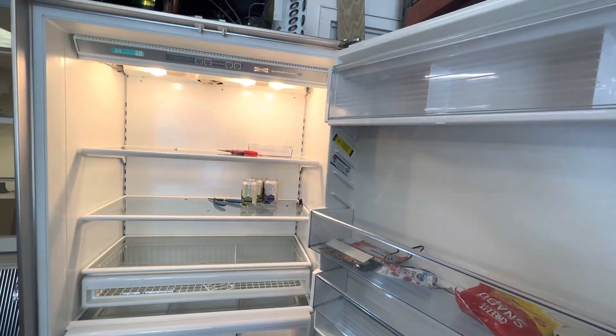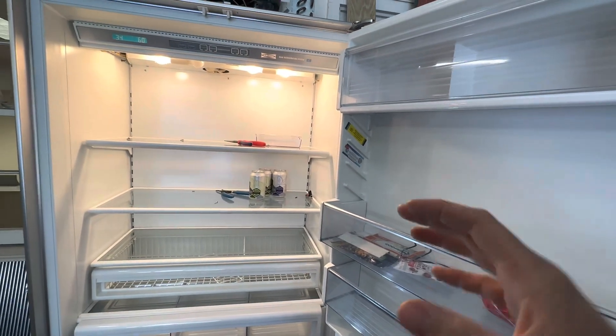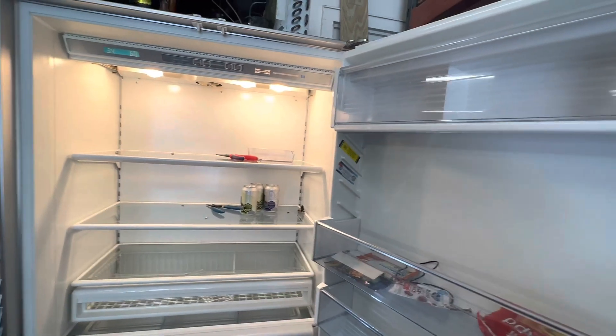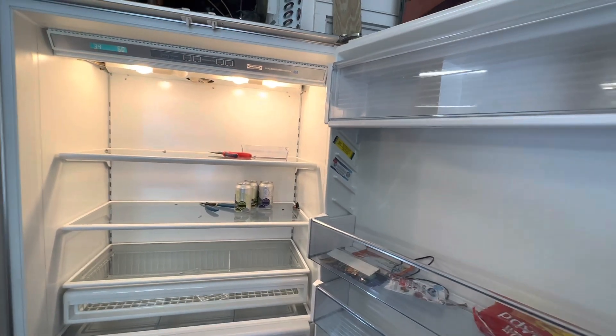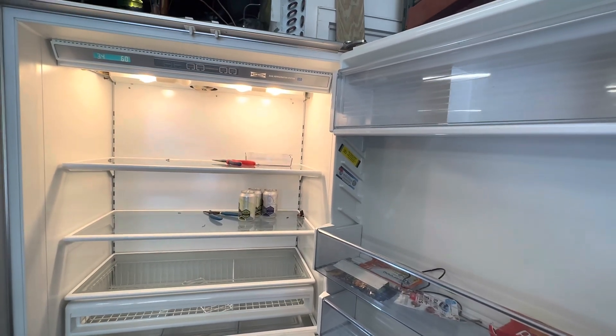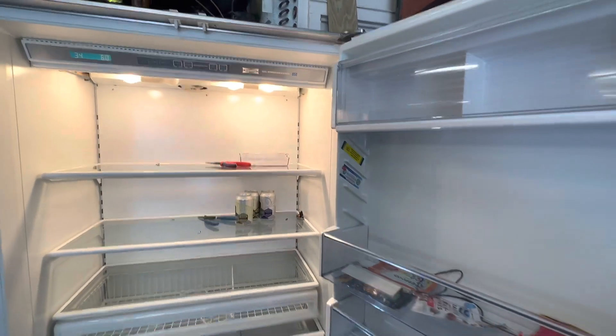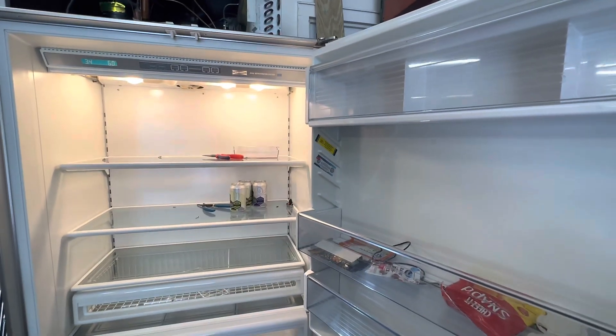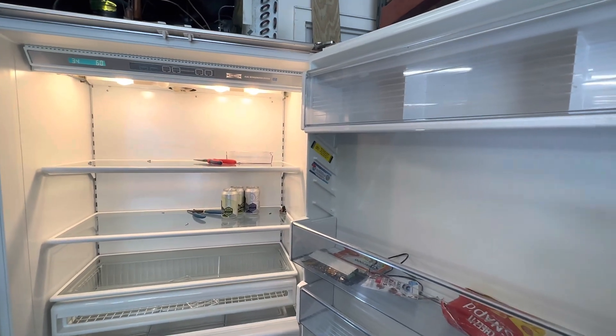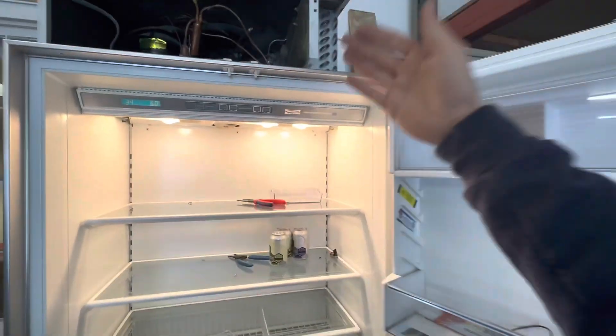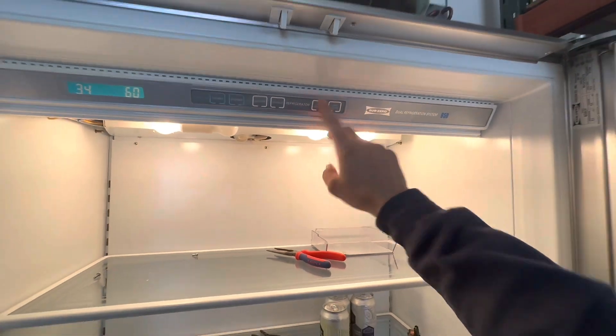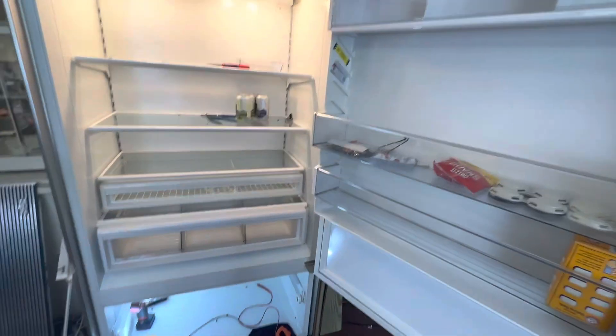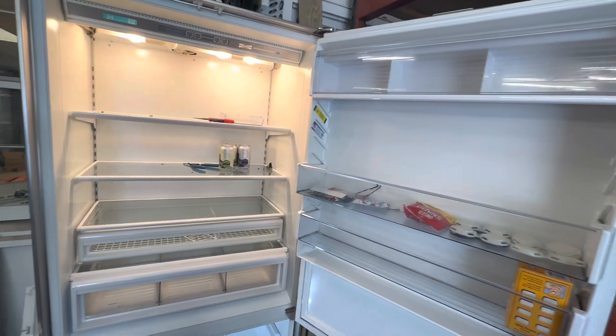But regardless, there's a lot of common sense you have to use when diagnosing these issues. But what I've shown you is that the power always comes from the control board. It goes through to your terminator. If your terminator is working, it'll go through to your defrost heaters. And if that is the whole system, then you can start to devise what is wrong and what isn't wrong using a volt meter and constantly putting it into a manual defrost and checking your power in different areas of the machine. I hope that helps.